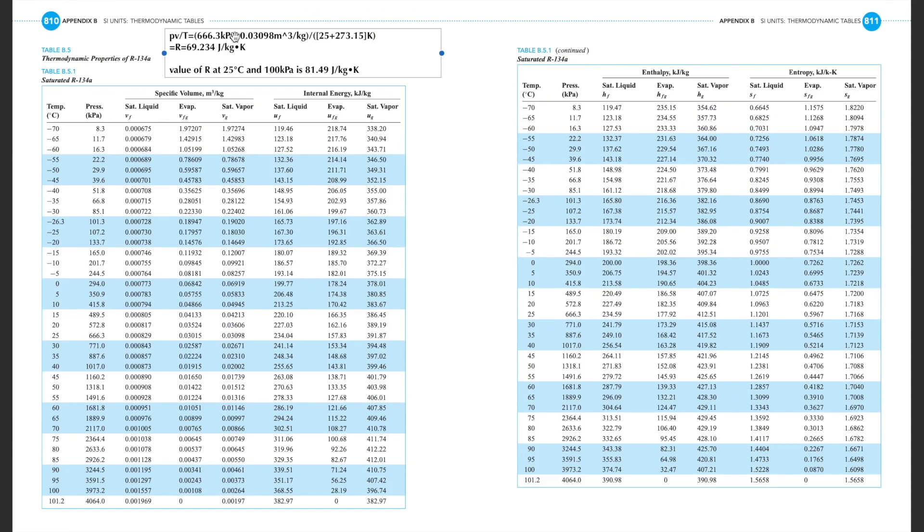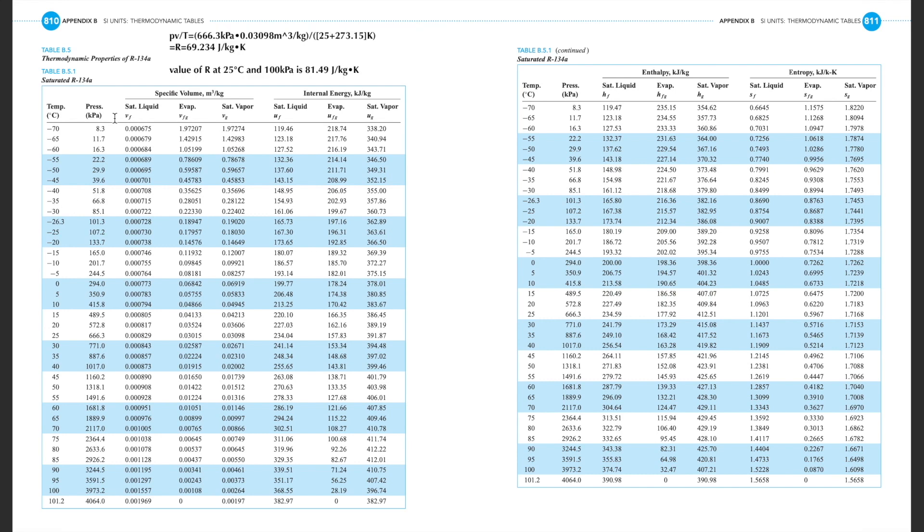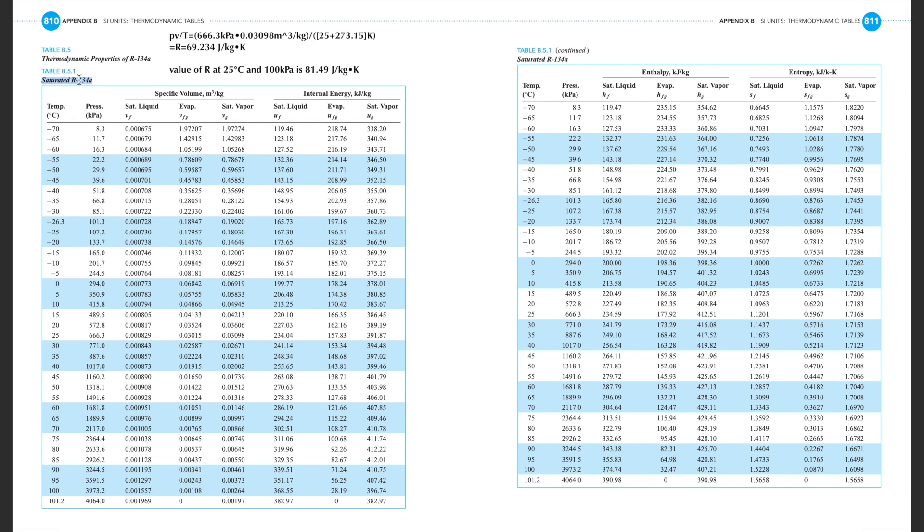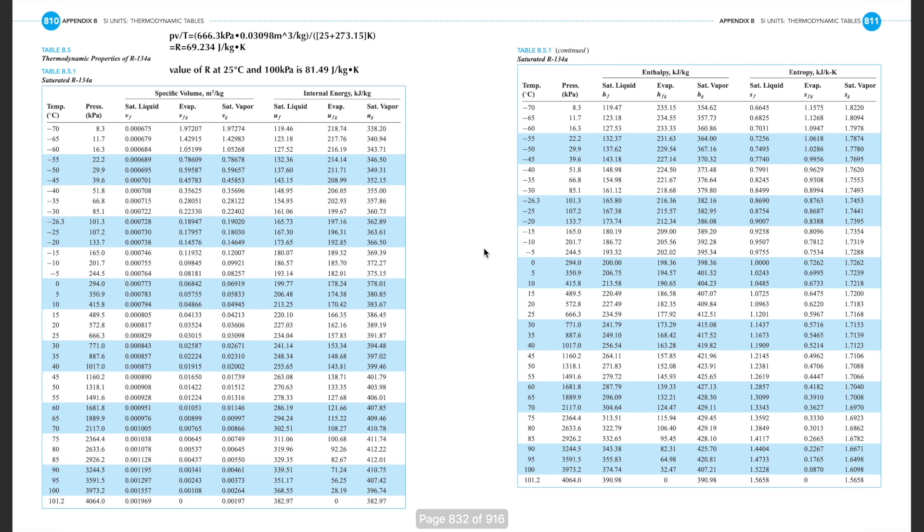Basically, to get water to boil at room temperature, 25 degrees Celsius, we need to put it in an environment where the atmospheric pressure is 3.169 kilopascals, which is not a lot. We got to go on to R134A and we're going to talk about what properties are important. So you can see I've left some notes here as this is a very important page for me, but we're just going to focus on what's in these tables. So at 25 degrees Celsius, we see that R134A boils at 666.3 kilopascals. What exactly is this telling us?